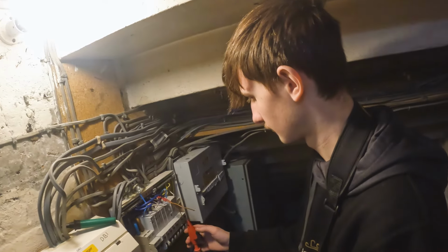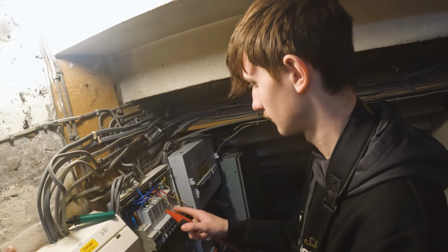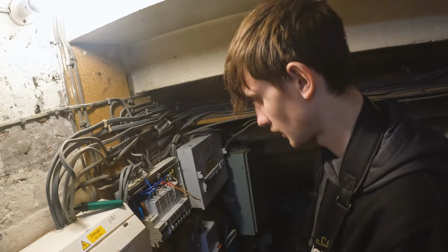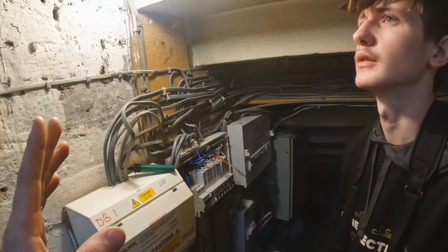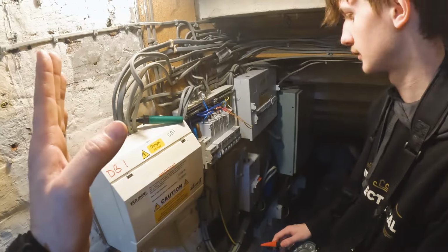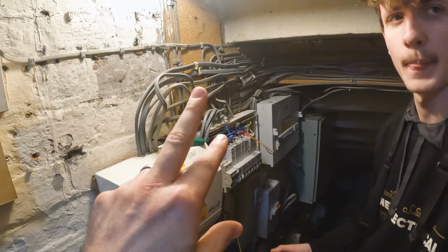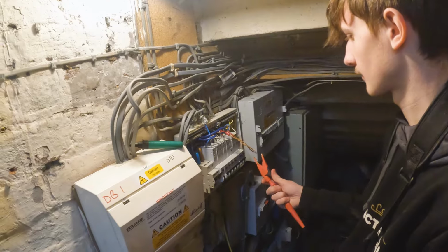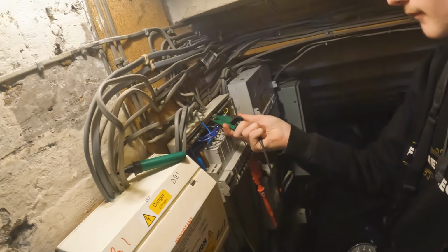So what are we going to test then? Where do you think you start? Well, you can test on this. Would you start at a low resistance? Well, yeah. So, continuity. It's that test between what then? 0 and greater than 2,000. So this tester tests between 0 ohms and greater than 2,000, and if it's outside that, it'll just say greater than 2,000 if you test between two conductors. So let's test at that and see if we've got any short circuits. This will prove, unless the appliance powers on and then it short circuits, if we've got any dead shorts currently.